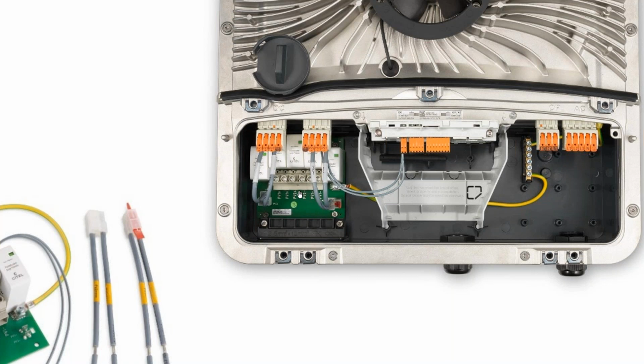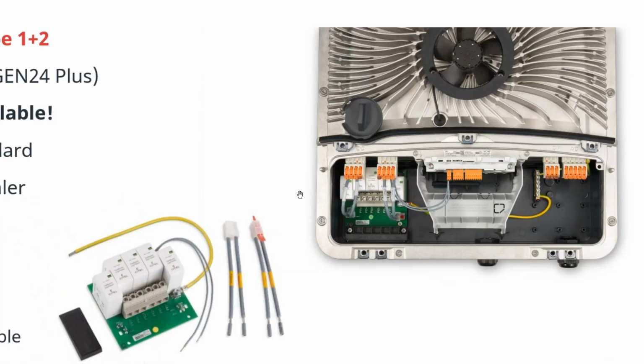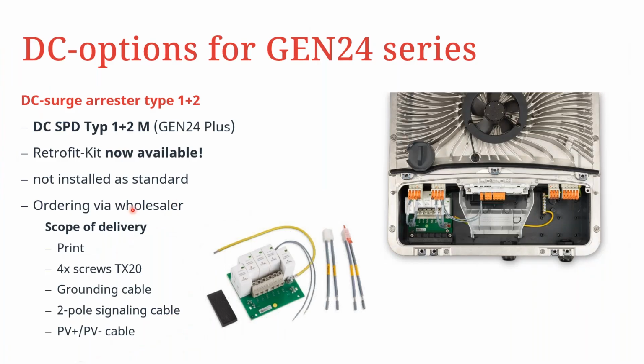This would normally be ordered through your wholesalers or your Fronius distributor. It would be provided as it is here, with 4 screws, a grounding cable, a 2-pole signaling cable, as well as PV plus and PV minus for connection to the DC area. As you can see, the connection is on both sides of the DC connection area.